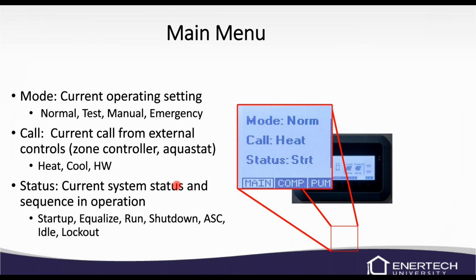The main menu, if you press the main button, it's going to show you the current operating setting, and that could be either normal mode, test mode, manual, or emergency mode. The call is the current call from the external controls. So it's either going to be heating, cooling, or hot water. It's going to show your status. And that status could either be startup, equalize, run, shutdown, ASC, idle, or lockout.